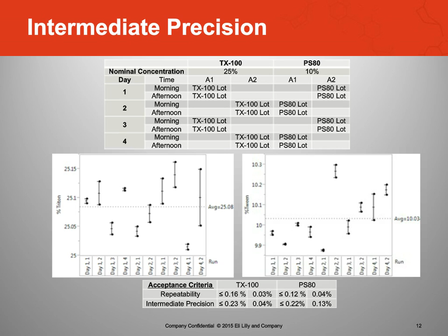Repeatability had an acceptance criterion of less than 0.16 for Triton and 0.12 for Tween, and intermediate precision, which is a combination of within run and between run, had 0.23 and 0.22, about the same. But we clearly met those acceptance criteria in both cases. For Triton we got repeatability of 0.03 and intermediate precision of 0.04. Tween was 0.04 and 0.13. So having met the acceptance criteria for intermediate precision, we felt comfortable and continued on with the validation.